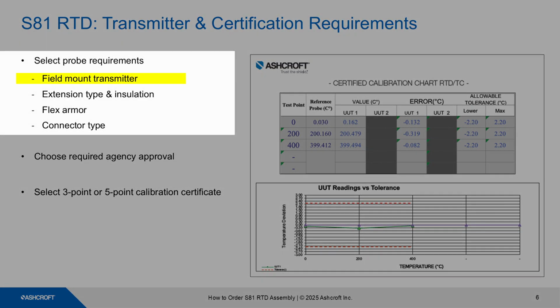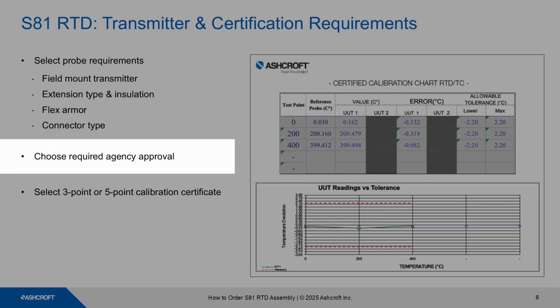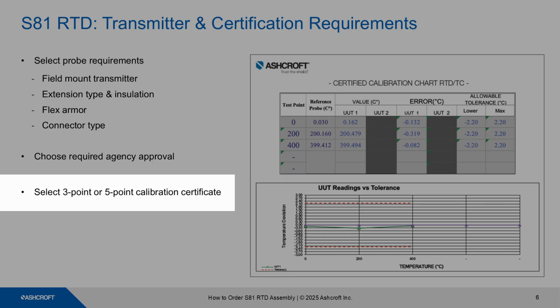A transmitter can be mounted in the remote head. Now you need to select the extension wire type and insulation. There are also options for flex armor or connectors that may be required. If needed, the required agency approval will be based on the area classification and method of protection. And a 3 or 5 point calibration certificate may also be required.